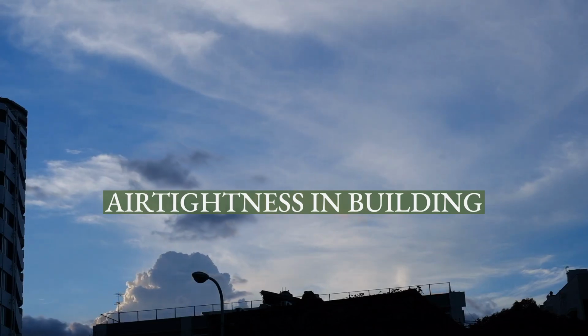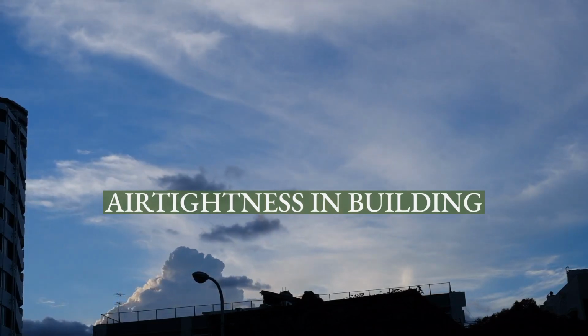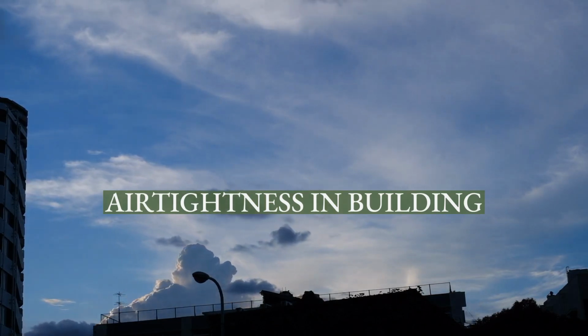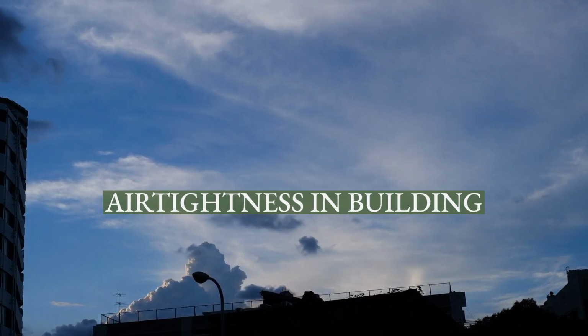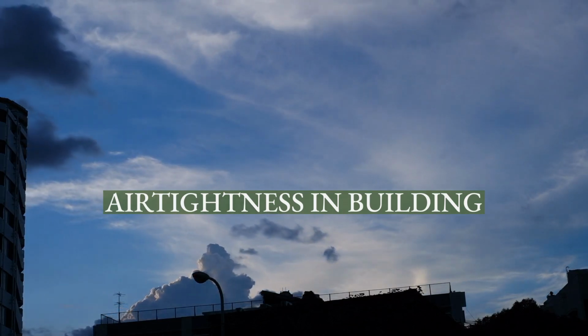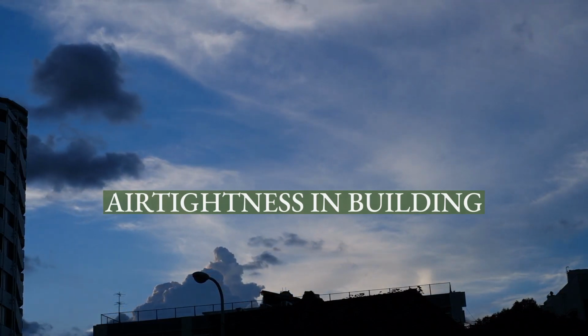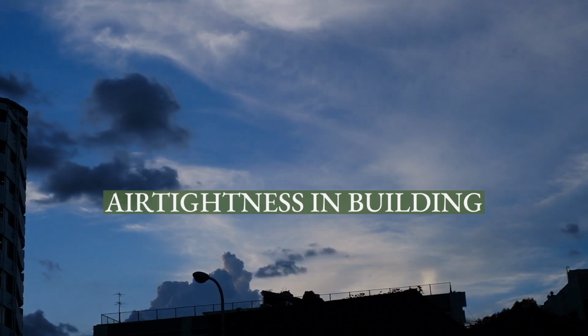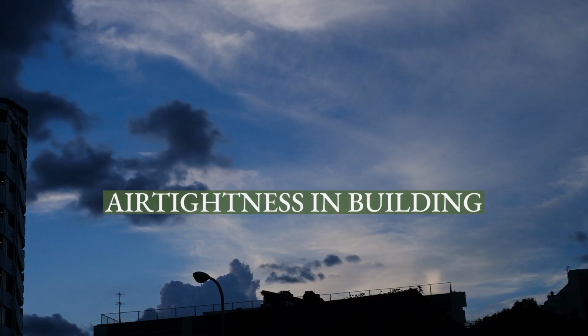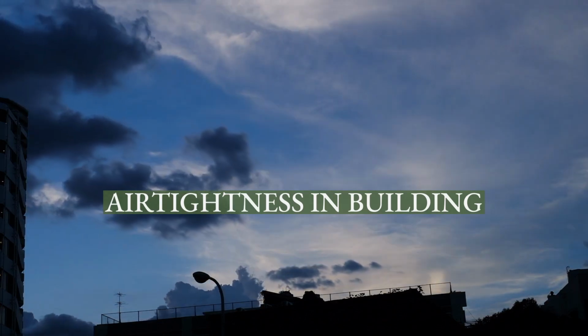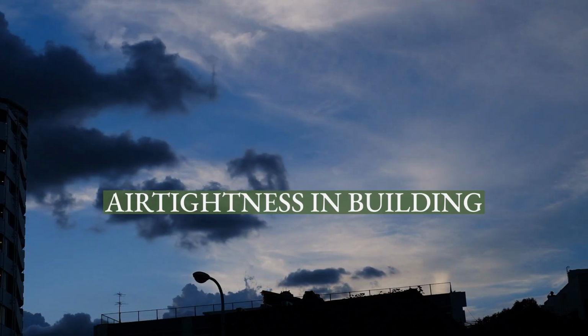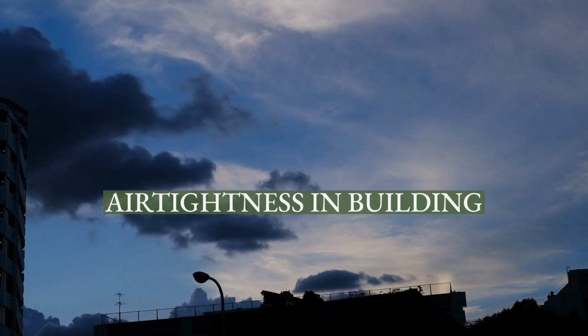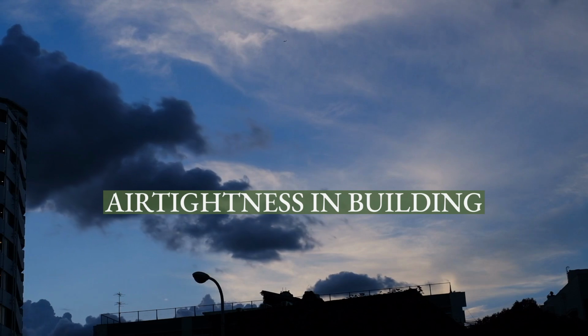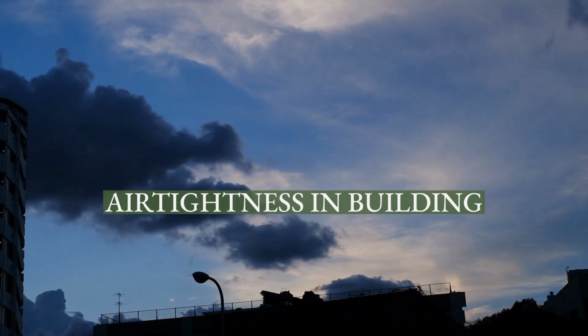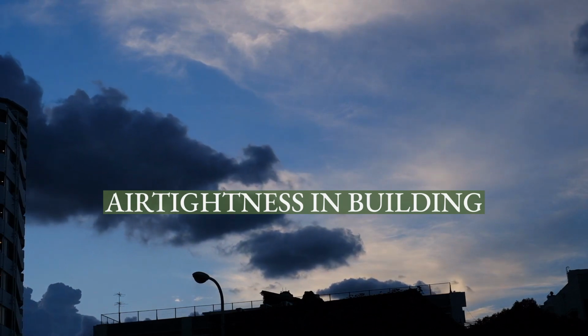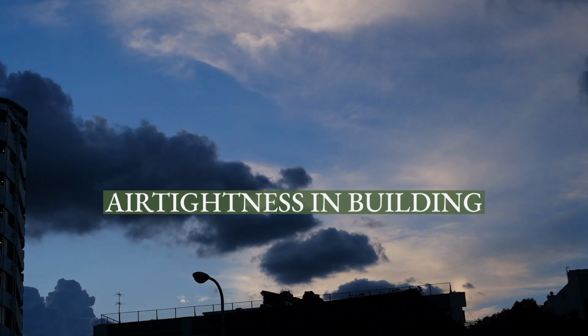Now, we shift our focus to airtightness in buildings, a topic that deserves our attention. The most common technique to measure airtightness is the fan pressurization method, also known as the blower door test. It is measured by the number of air changes per hour, ACPH, that occur when there is a differential pressure of 50 pascals between outside and inside the building. If an air volume equal to the inside volume of the building flows across the envelope in 1 hour, then ACPH = 1. Airtightness improves buildings' energy performance since low airtightness levels imply high infiltration rates, drafts, risk of condensation, and moisture accumulation, and other effects.